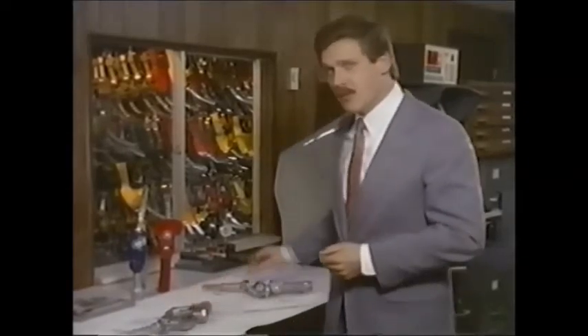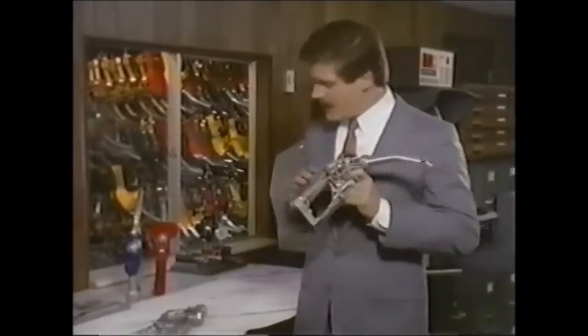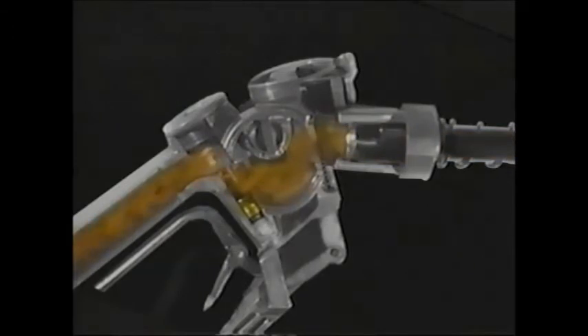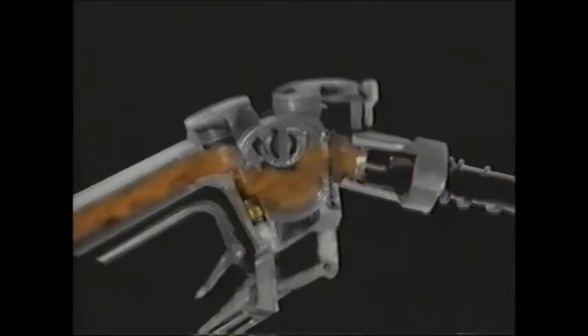How does Husky Protector 10S prevent a spill? Husky's new design incorporates a double shut-off in the body of the nozzle. Like the ordinary nozzle, it shuts off when the tank is filled. But it also shuts off when pump pressure drops, thanks to a second spring-loaded rolling diaphragm — that's a key difference. When the customer turns on the pump, gas at usually 20 pounds of pressure forces the rolling diaphragm into the open position. Fuel flows as long as pressure is maintained. But when the pump shuts off the pressure, the second diaphragm closes and forces up the regular diaphragm, which shuts the poppet valve and stops the flow. Simple and effective.